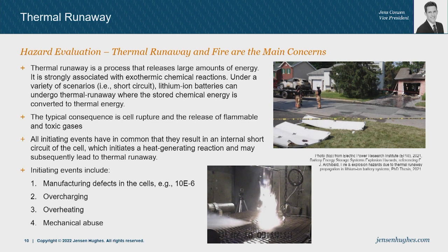What causes it is a short circuit, as I mentioned earlier. But what causes the short circuit? Typically, we distinguish four main things. One is a manufacturing defect. When we make a lot of batteries, every now and then we're going to have a bad apple. It could be every 1 million or 10 million cells that there's a bad cell involved. The second one is an overcharge condition. When we make batteries, we have charge and discharge operations to test the cell. That is where stuff can happen, in particular when we overcharge or overheat. And the last one is a mechanical abuse situation, where a cell was dropped or something like that.